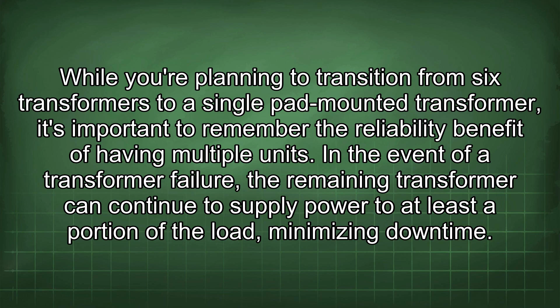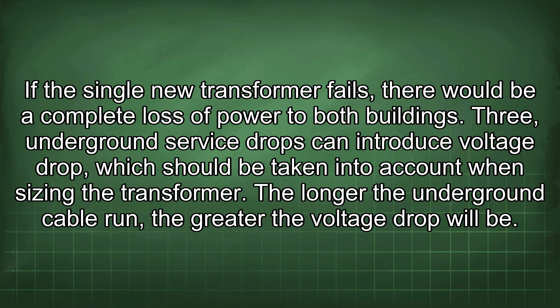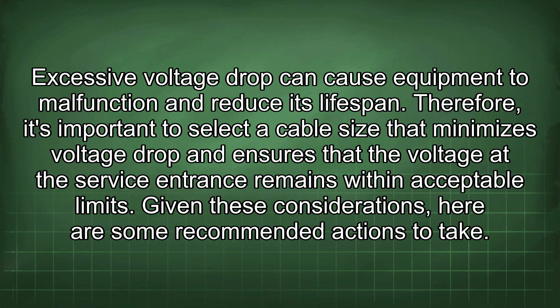3. Underground service drops can introduce voltage drop, which should be taken into account when sizing the transformer. The longer the underground cable run, the greater the voltage drop will be. Excessive voltage drop can cause equipment to malfunction and reduce its lifespan. Therefore, it's important to select a cable size that minimizes voltage drop and ensures that the voltage at the service entrance remains within acceptable limits. Given these considerations, here are some recommended actions to take.